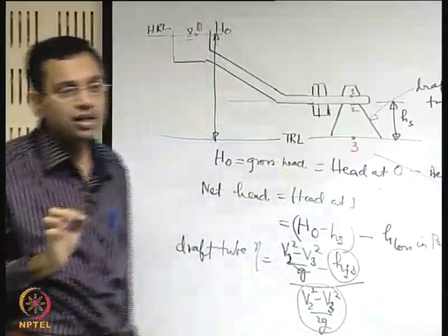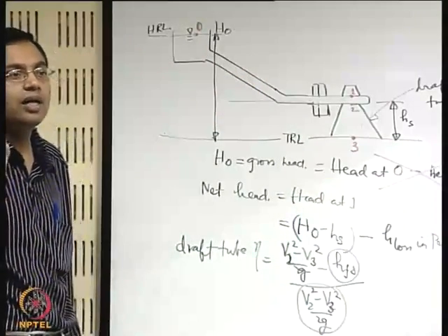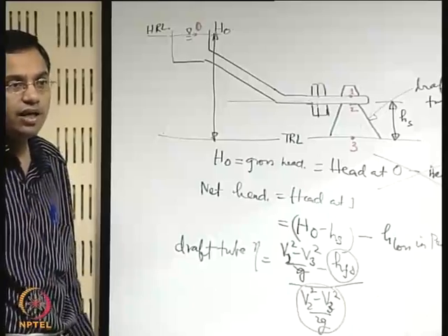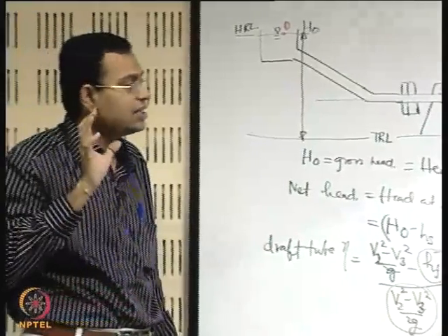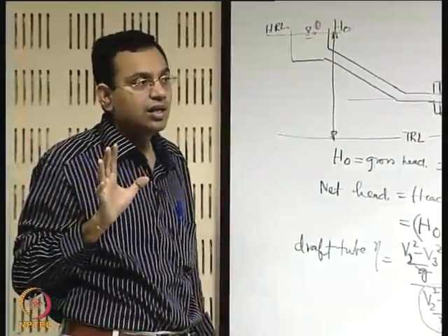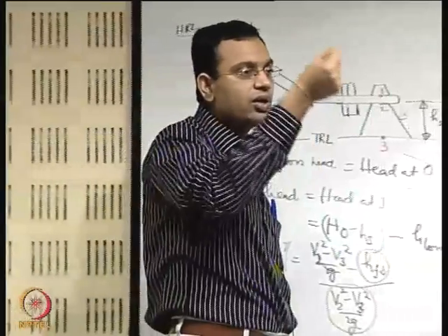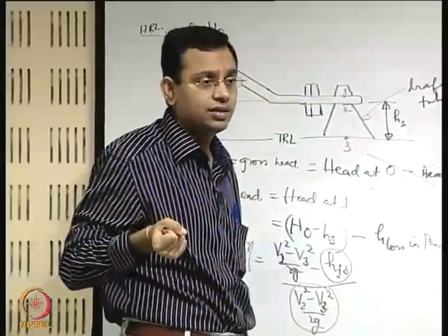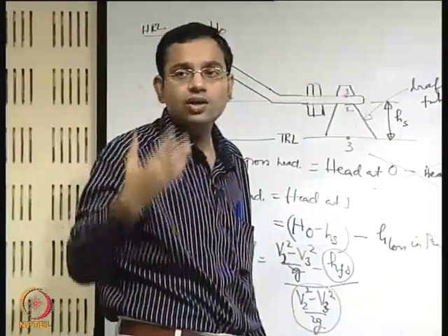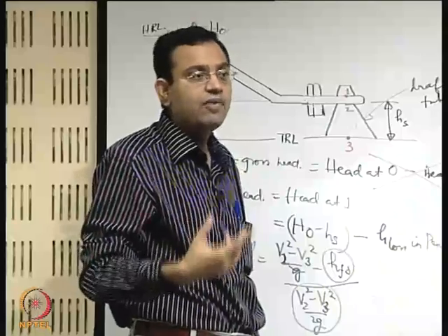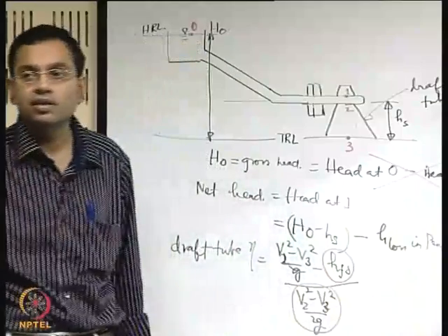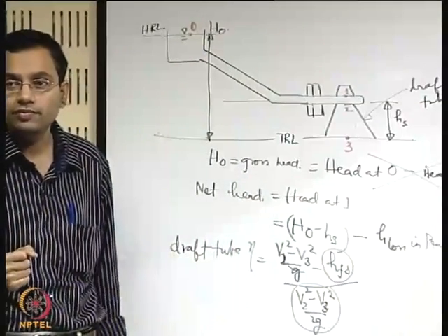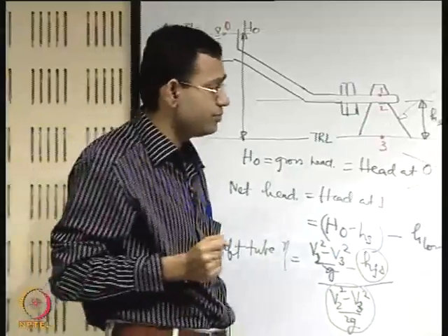The other thing is that, will the impulse turbine have a cavitation prone behavior? Again, the answer is no, because cavitation is because of the local variation of pressure within the turbine. In the impulse turbine, there is no local variation. Therefore, cavitation is an irrelevant phenomenon for an impulse turbine, that we have to keep in mind.